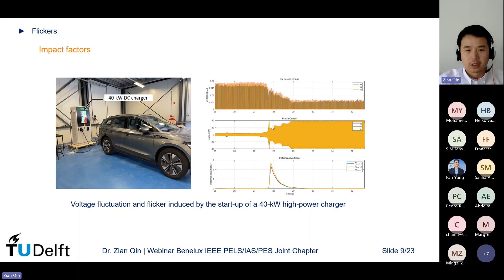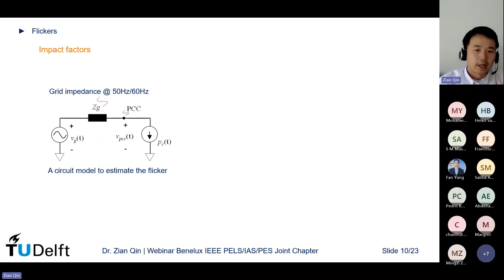So to model the flicker issues, what you need is a circuit like this. You can model the grid as a voltage source together with a grid impedance. Impedance is a word that I'm going to talk about very often in this webinar, but every time I talk about impedance, it is a bit different. For instance, to model the flicker, you only need to know the grid impedance at fundamental frequency. That's it. Then on the charger side, you don't need to model the dynamics of the charger as an impedance. That is not necessary. What you need is a charging profile. You need to know the charging power as a function of time. That's it. With this, you can model the flicker issues.